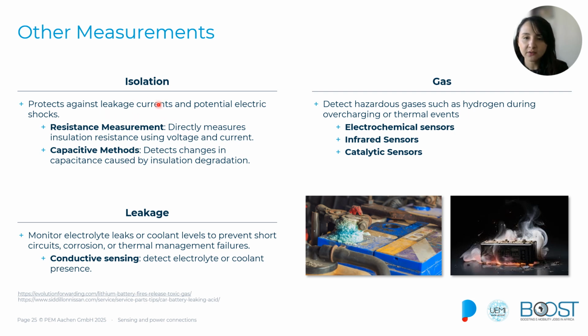For measuring the insulation of our system, we have two main methods: resistance measurement, which directly measures the insulation resistance by applying a small voltage and monitoring the current flowing through that loop; and capacitive methods, where we measure changes in capacitance and how that relates to, for instance, the degradation of the insulation.